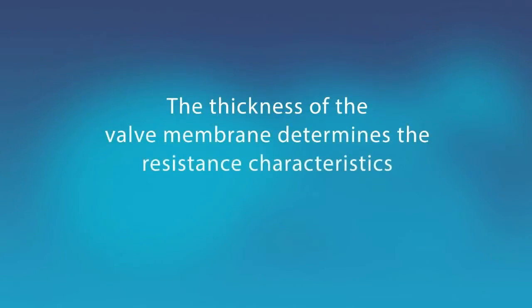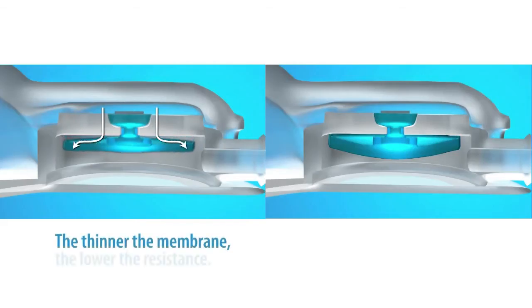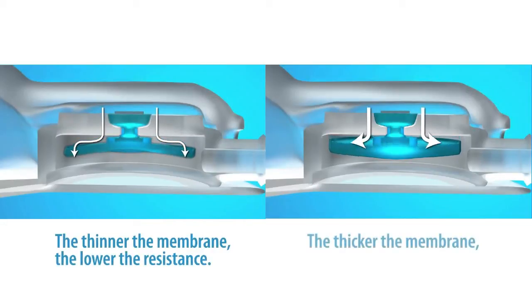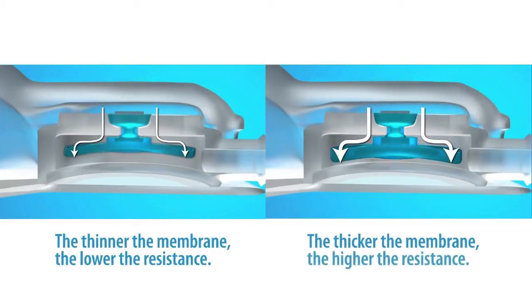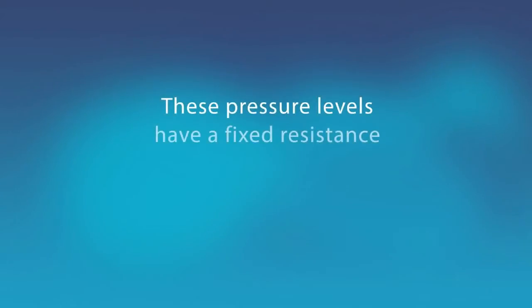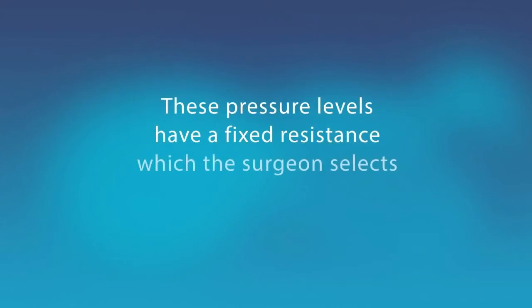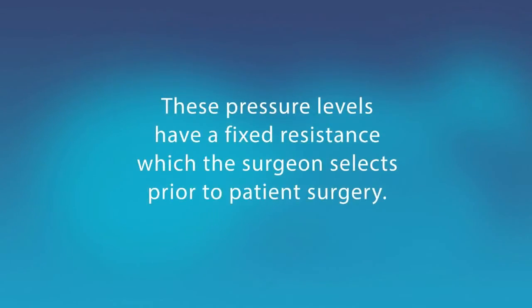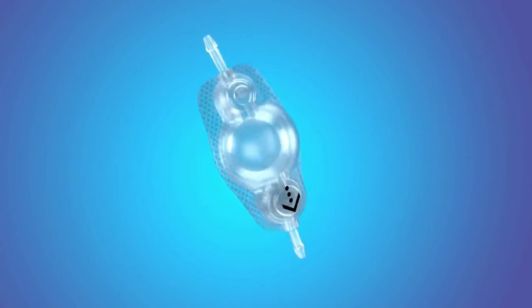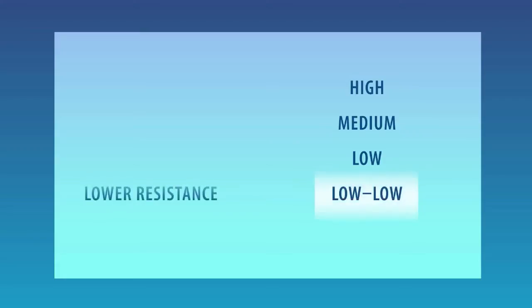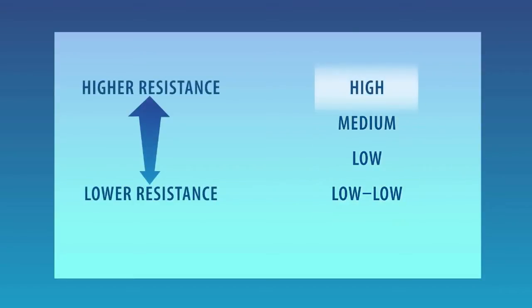The thickness of the valve membrane determines the resistance characteristics of the valve. The thinner the membrane, the lower the valve resistance; the thicker the membrane, the higher the valve resistance. These pressure levels have a fixed resistance, which the surgeon selects prior to patient surgery. The contoured valve is available in four fixed pressure levels: low-low, low, medium, and high.